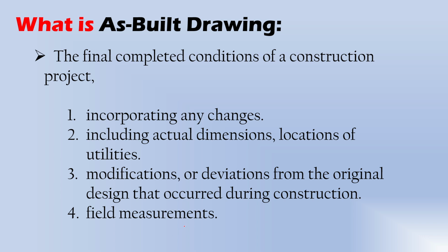And the last one is the field measurement. You should update your drawing with the field measurements. Whatever the site condition measurements are, you should update them. This as-built drawing, we are going to make when the building is completed. The changes which were done after we got approval of the shop drawing are the changes we include in this drawing. We will submit it to the consultant, take approval again, and submit to the client for their future reference. This is called as-built drawing.